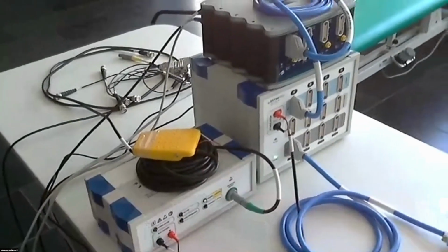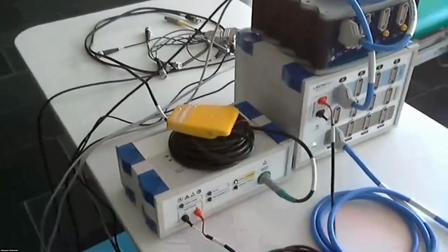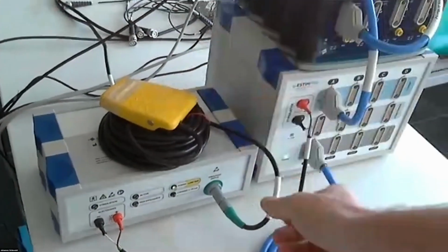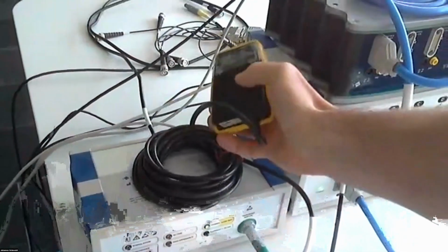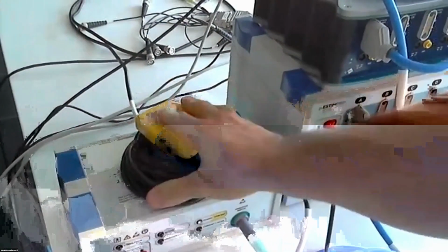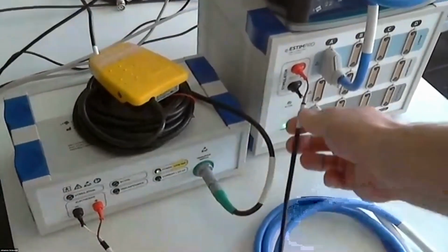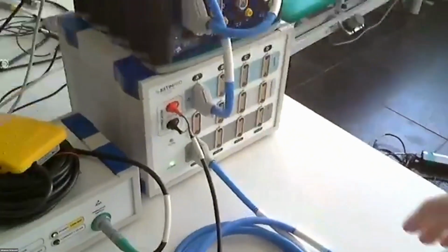Here you can see, actually it's mirrored. Anyhow, you can see the stimulator here. We have the foot switch connected, which is the safety feature, and it always has to be pressed, so I fixed it with the tape. Never do this in a real scenario, please. It's just for demo purposes. The stimulator is connected to the switching unit, which you can see here. The switching unit receives signals from the electrodes, which I'll show in a second, and it forwards the signals to the g.HIamp, which is located on top here.